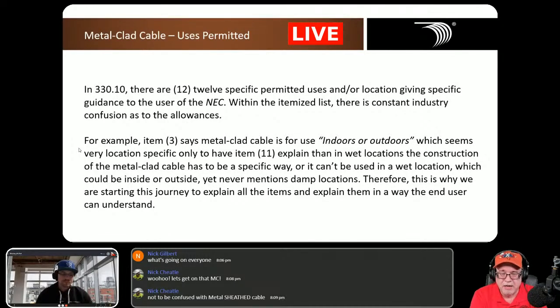We're talking about interlocked because there are different types: smooth, corrugated, or interlocked. Smooth is also called continuous. The interlocked is a tape configured and interlocked as it wraps around the conductors fed through a cabling machine, whereas smooth and corrugated are a continuous extrusion of sheathing over it.